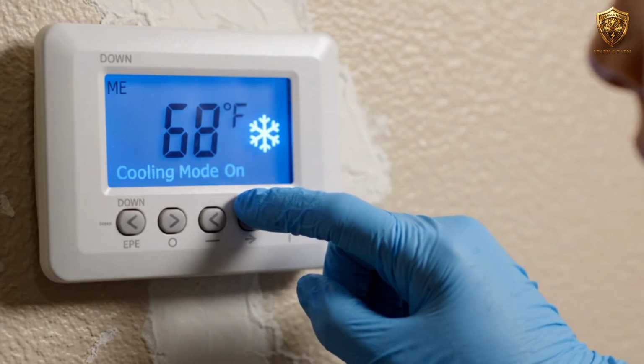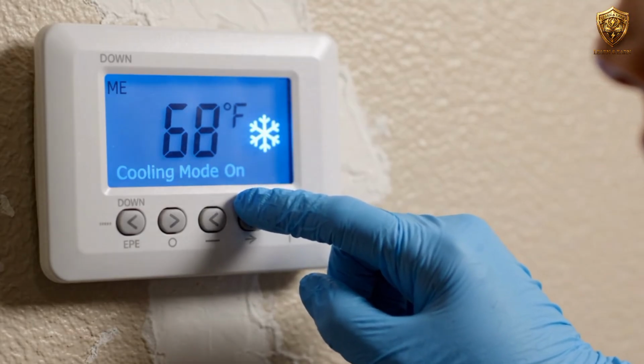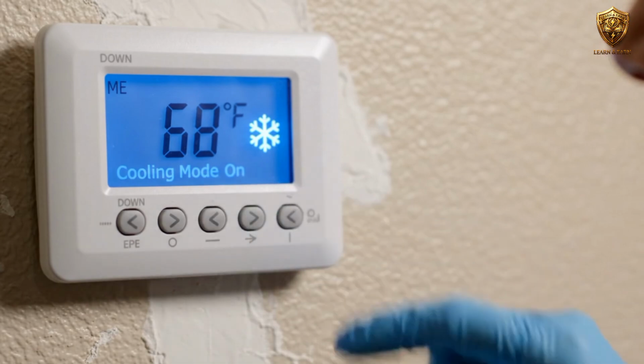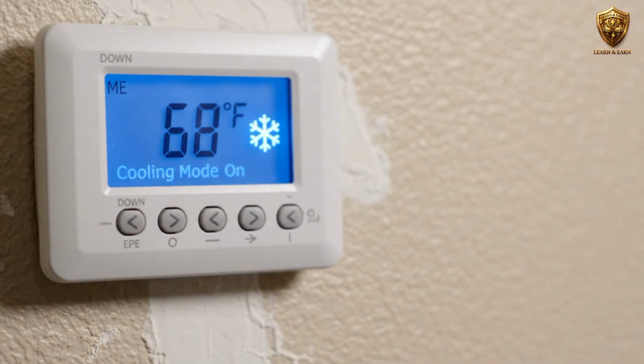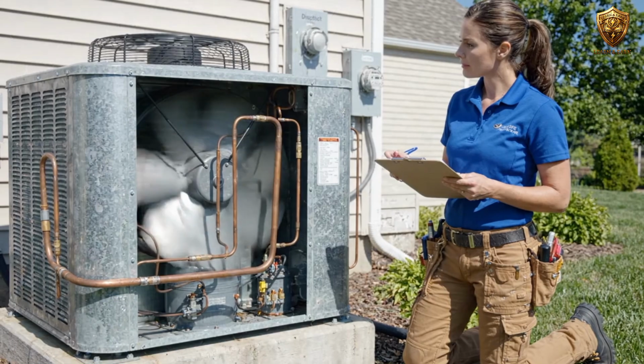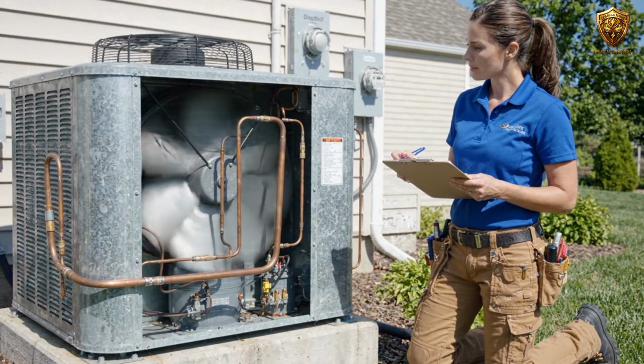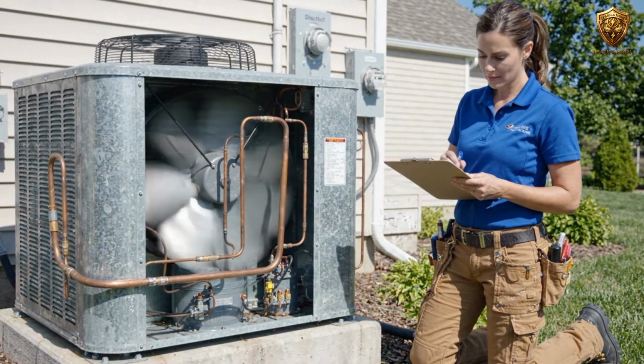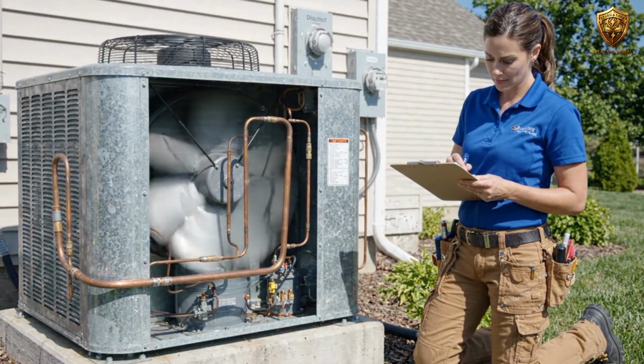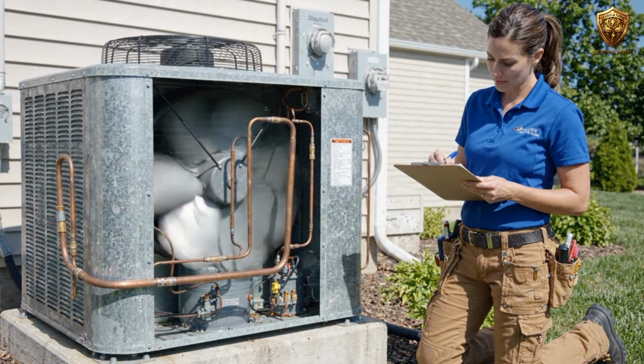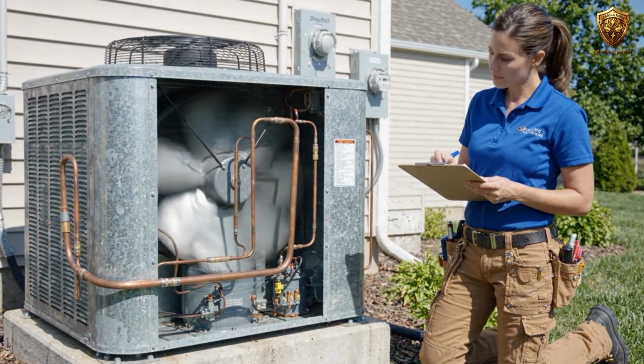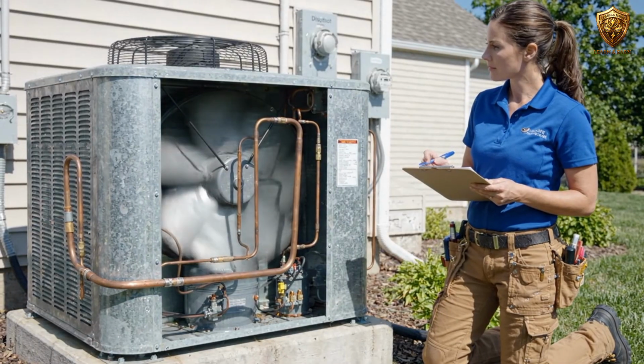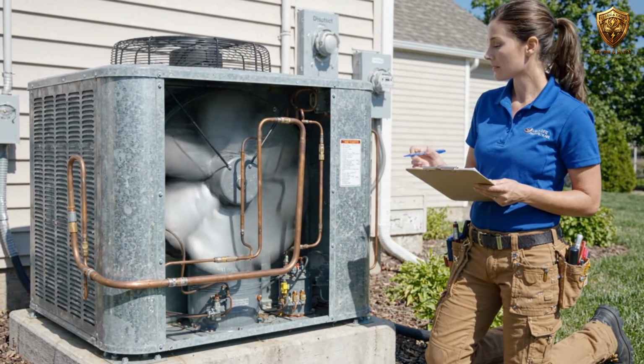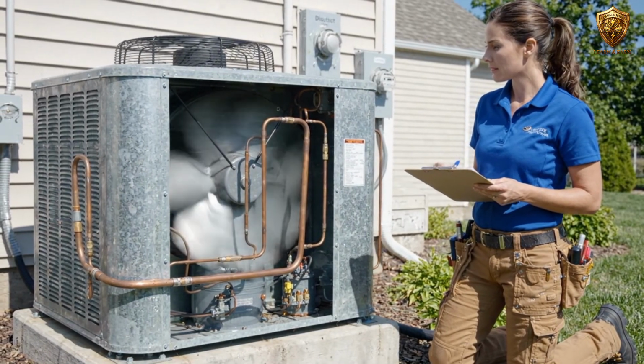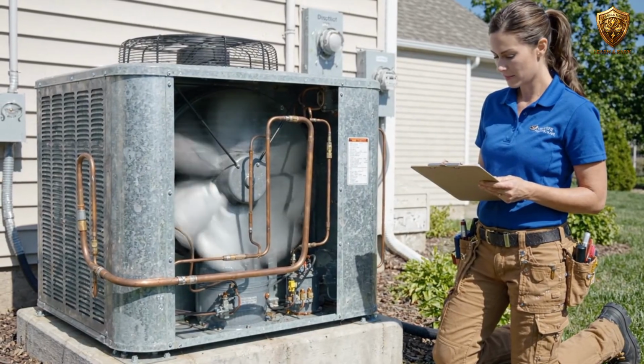Start with the thermostat and system status. Confirm that the system is actually calling for cooling and that the set temperature is below the current room temperature. Then observe what happens. Does the indoor fan start? Does the outdoor contactor operate? Does the condenser fan start? Does the compressor attempt to start? Does the breaker trip? Does the system make an unusual humming or clicking sound? These sounds and actions are clues.